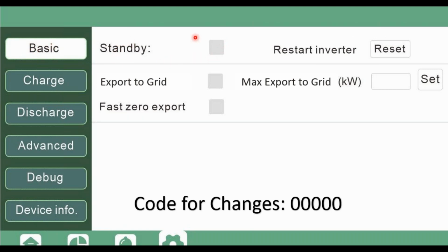When you enable standby, you will put the system in complete standby, where there will be no PV production or load output from your batteries. However, it will still do AC pass-through. And that's a really, really good feature, because when we do firmware updates, let's say remotely or locally, we always recommend putting the system in standby, and then the homeowner might not even know that their system is being updated. So for grid tie users, this standby feature is phenomenal. Installers can do this remotely. You can ask us to do it for you, no biggie.